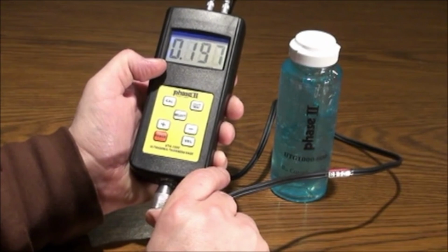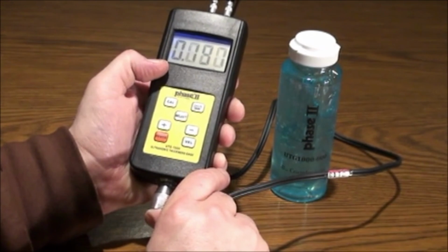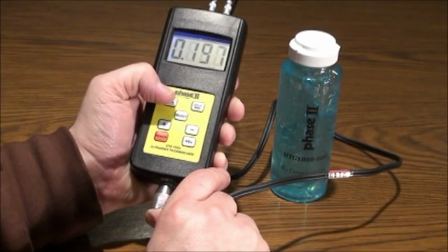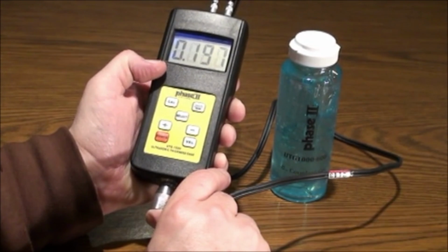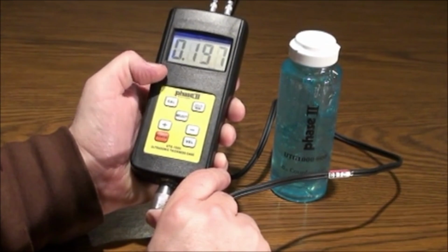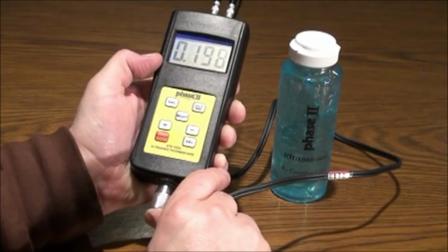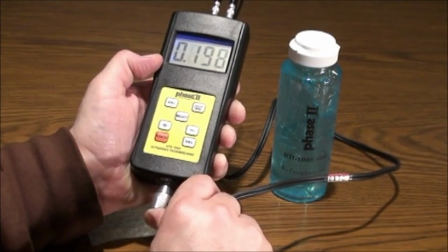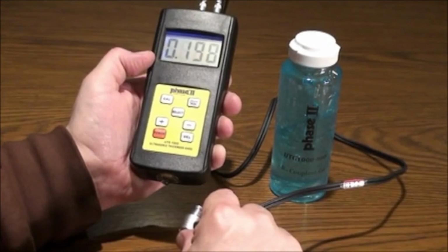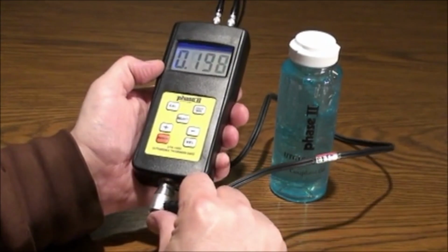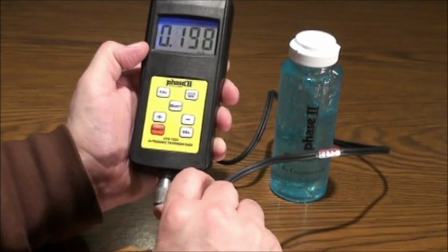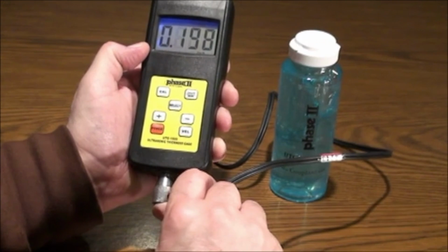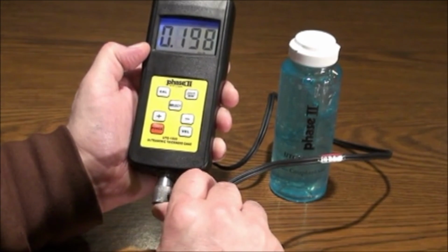The reading should be 5 mm or 197 thousandths. This will flash with the Cal while still holding the probe to the block. Press Cal again to save. Remove probe from block. Now press the probe to the calibration block once again to confirm the reading is 197 thousandths or 5 mm. The calibration result will automatically be saved once confirmed.